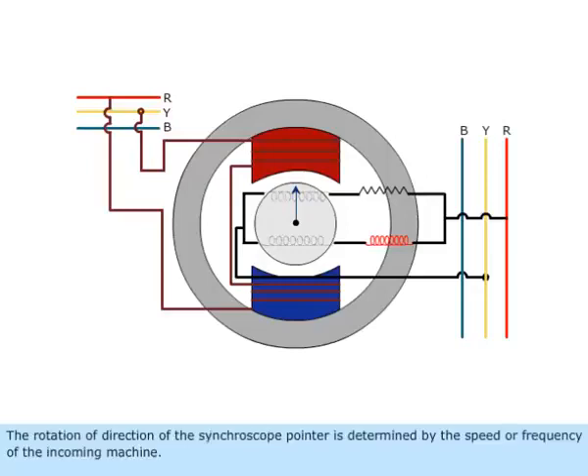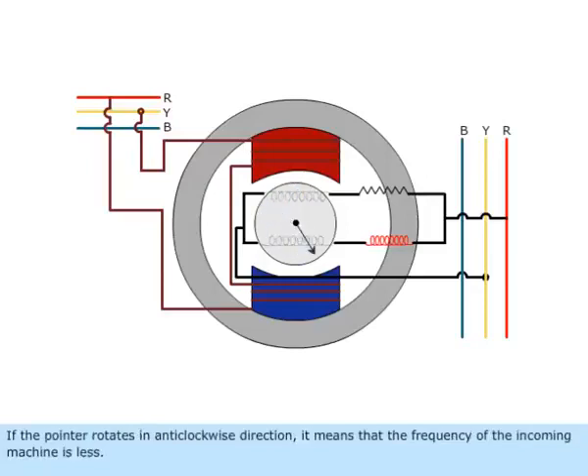The rotation direction of the synchroscope pointer is determined by the speed or frequency of the incoming machine. If the pointer rotates in anticlockwise direction, it means that the frequency of the incoming machine is less.